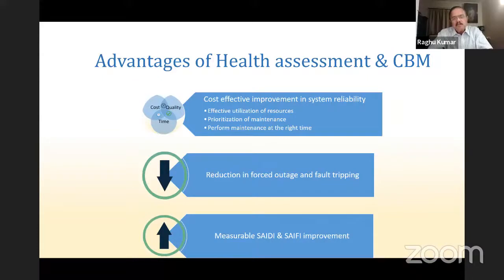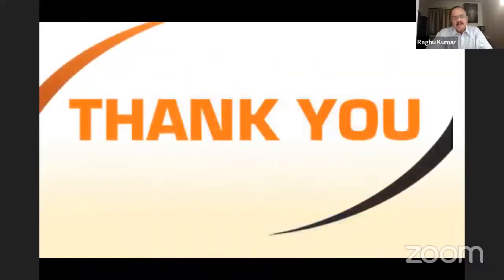And we reduce the forced outage and fault trippings. This can be measured using the reliability indexes like SAIDI and SAIFI, which are normally used in all utilities, one is a frequency index, one is a duration index. This will be reduced with this condition assessment and condition-based maintenance. Thank you. And this was the basic information. And whatever I know, I can answer if you have any questions.